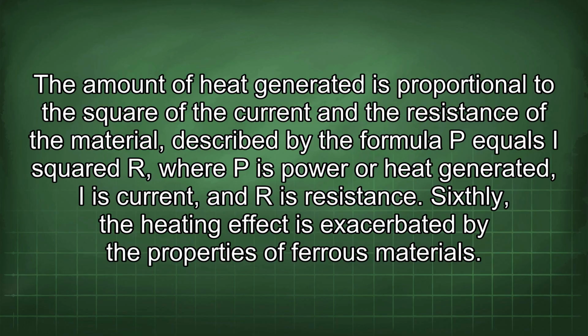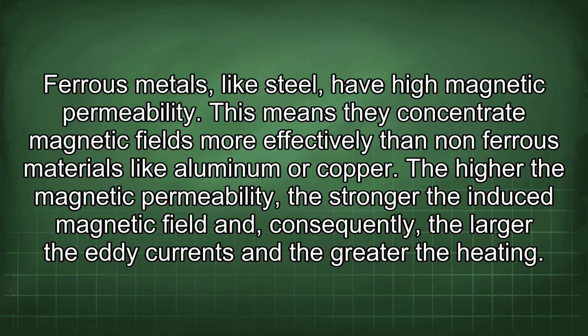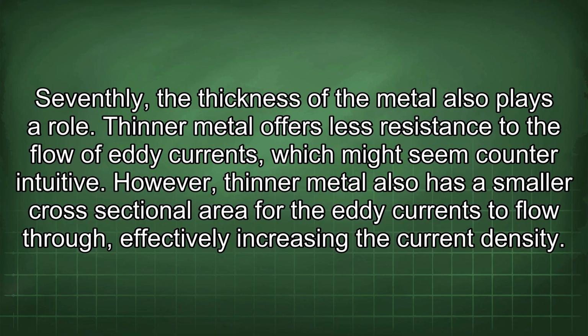The amount of heat generated is proportional to the square of the current and the resistance of the material, described by the formula P equals I squared R, where P is power or heat generated, I is current, and R is resistance. Sixthly, the heating effect is exacerbated by the properties of ferrous materials. Ferrous metals, like steel, have high magnetic permeability. This means they concentrate magnetic fields more effectively than non-ferrous materials like aluminum or copper. The higher the magnetic permeability, the stronger the induced magnetic field and, consequently, the larger the eddy currents and the greater the heating.